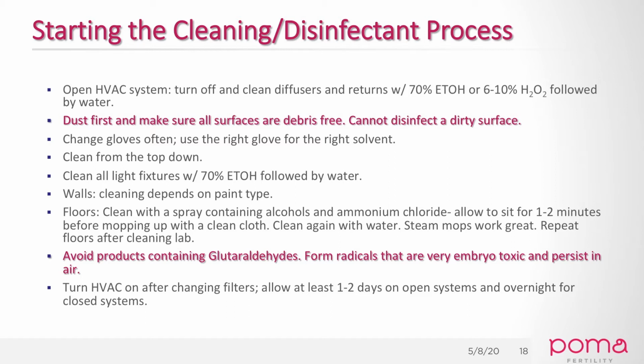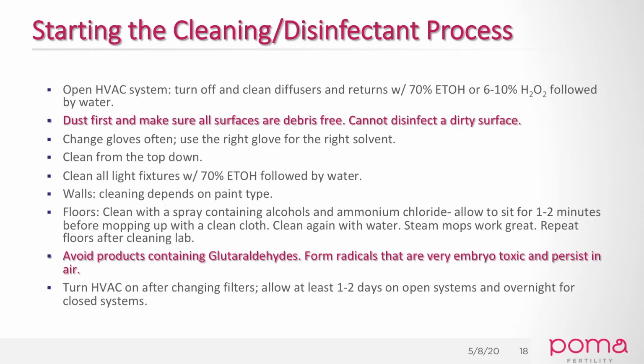Again here, now that you're actually inside your facility cleaning, you really need to think about what to clean with. Don't use glutaraldehydes. The reason for that is that glutaraldehydes are really effective cleaners. In fact, glutaraldehydes are used a lot for cold sterilization. The problem with glutaraldehydes is that they break down and form radicals that are extremely embryotoxic, and they persist for a long time in the air. In fact, in tissue culture labs, most labs don't use them because the glutaraldehydes end up impacting cell culture development after a cleaning. So please don't use glutaraldehydes.